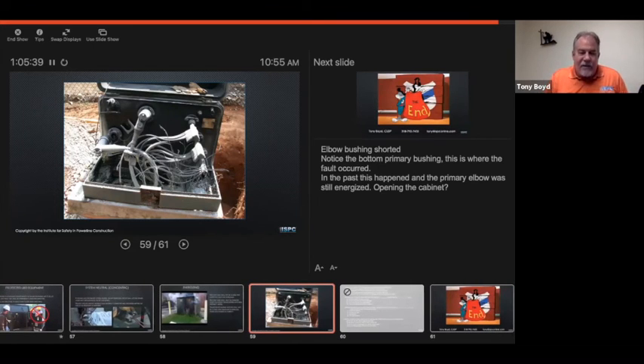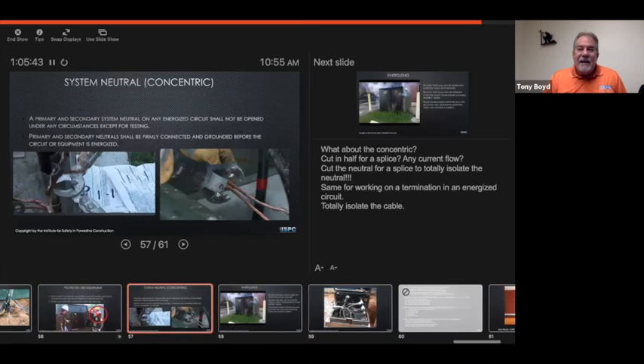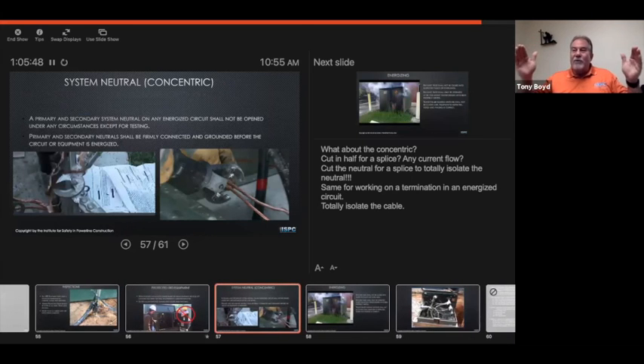All right, so I'm looking and I don't have my diagram for that concentric neutral, but in any case, we have a concentric neutral that's connected on both sides. We've switched out the primary cable to replace elbows or whatever, but that concentric neutral is still connected. It is a current carrying conductor, so if we ever get any voltage potential difference in there, will it shock us? And the answer is yes, it might. Okay, so it's not a real big hazard, but it is a hazard that I like to bring up in all of my training. If we're making a splice, what we should do on each end of that cable is just get a bond, any kind of bond that would bond those two together, so that when we go to grab them and put them back together, we're not getting in between that current carrying conductor. Would you ever cut an overhead neutral and get between it?